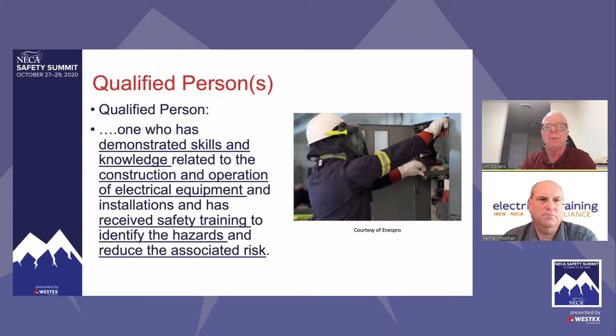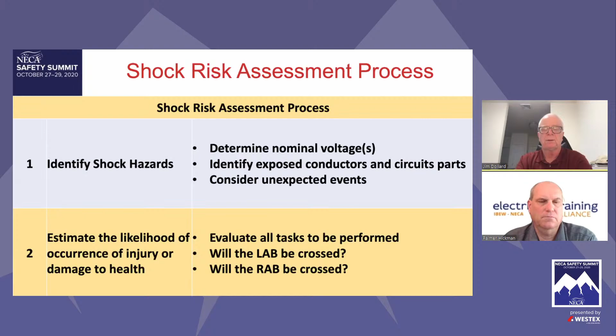By definition, the arc flash boundary is at 1.2 calories, and it's determined through an incident energy analysis or by the PPE table. Palmer and I went over the requirements for shock risk assessment, and I'm not going to go through everything here because we are running out of time, but this really lays out, and it's part of the shock and arc flash risk assessment guide, for that trained person, for the qualified person, how to walk through the shock risk assessment process. So step one, identify shock hazards. And this is what they need to do: determine voltages, identify exposed conductors and circuit parts, consider unexpected events, estimate likelihood. Are we going to cross the limited approach boundary, the restricted approach boundary?